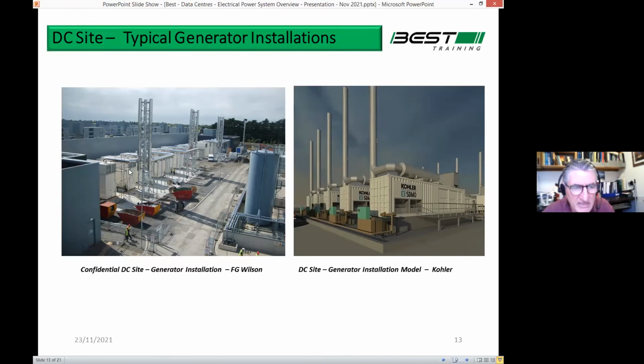But you can see them there. They're the generators in the containers. So these are normal shipping containers, the roll on, roll off type containers. And you can see the chrome flues coming up, and they're going up this stack here. That's a lattice tower, a triangulated lattice tower. So in this case, it has one flue going up each of the three sides of the triangle, and way above the building line there. And then the next three generators go on to the next flue stack and so on. And then you'll probably find that that's on one side, just as I showed you in my diagram, and then they have a mirror image of that over the other side of the data center.